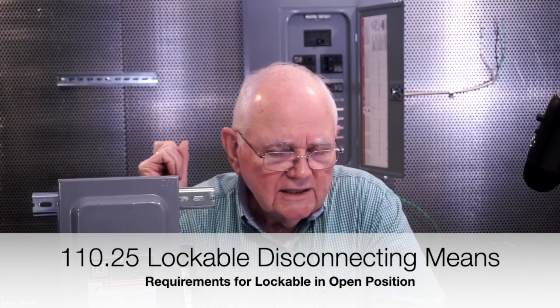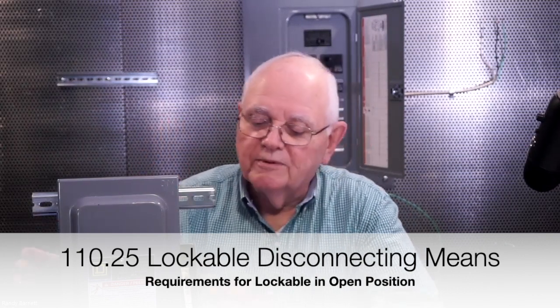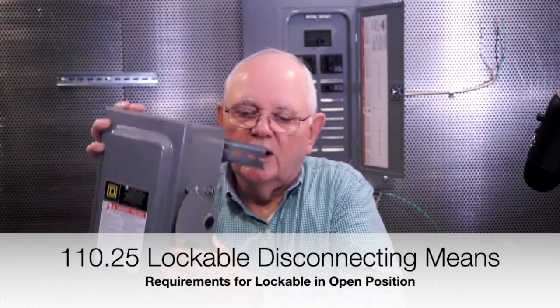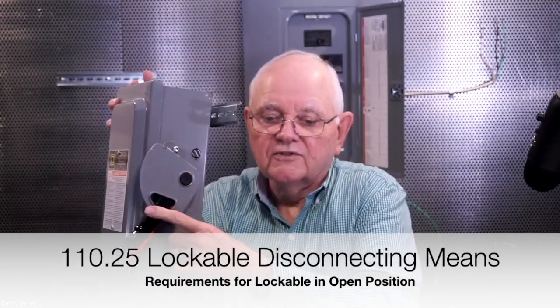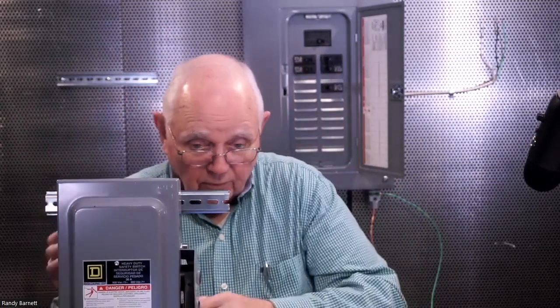Also, other than one and two family dwellings, I also have to mark on the front of this disconnect where the power source is for this disconnect. So if I have problems here, I know where to go to shut off the power to my disconnecting means. 110.25 says it has to be lockable in the open position. And so that's true. Once I open my disconnect, I can put a lock through here and lock it open. And of course, you think of lockout, tagout, don't you? In fact, that relates to a lot of the rules we see for motors in Article 430 for the location of disconnect. So that's another important one.